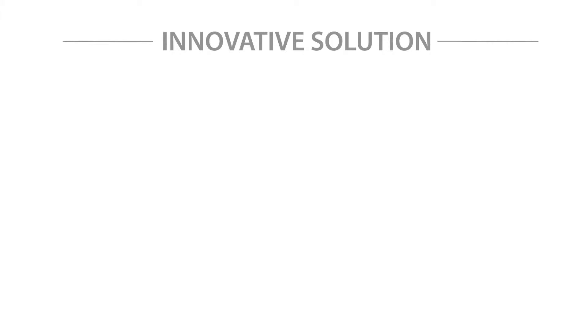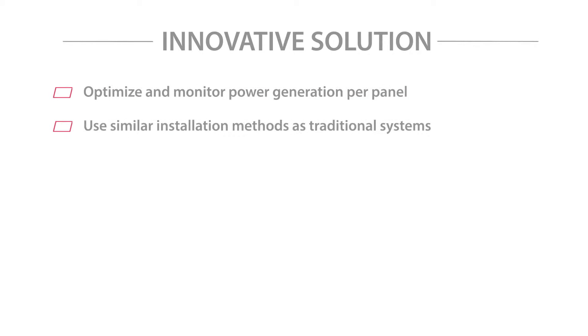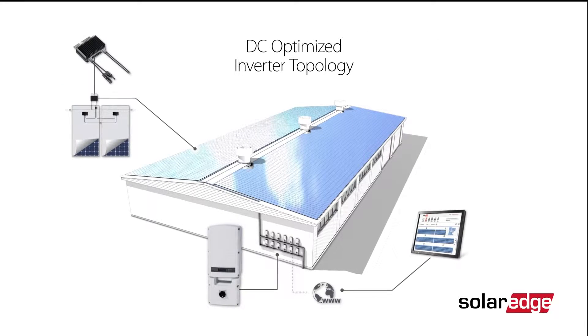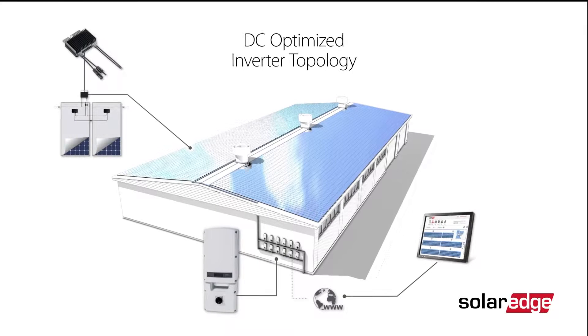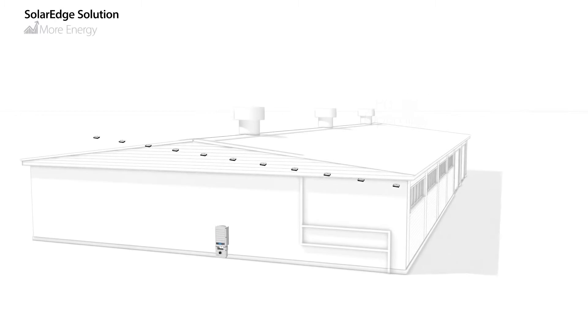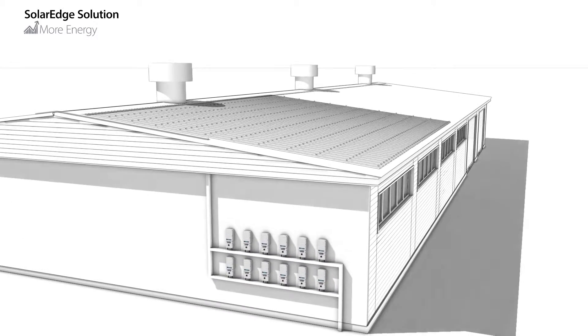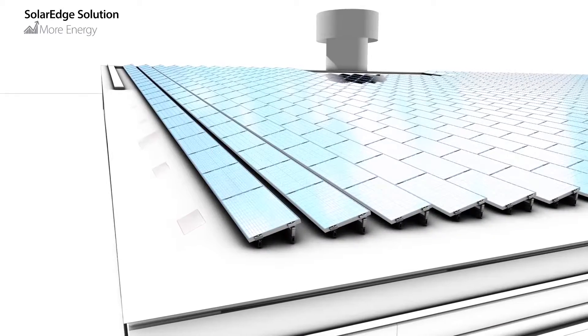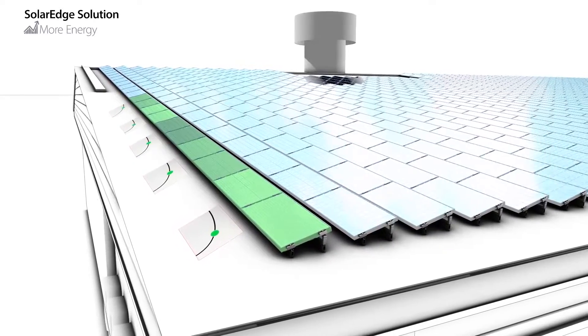When we started to develop the SolarEdge solution, we looked at the challenges posed by traditional systems and defined three goals: to optimize and monitor power generation of each panel; to use the same installation methods and components used to install traditional inverter systems; and to minimize long-term operation and maintenance costs. We developed a topology that meets all of these goals — the SolarEdge DC Optimized Inverter Topology. Our solution splits the traditional inverter functionality into two products: the power optimizer and a simplified inverter. The power optimizers are located on the panels, turning them into intelligent panels. These power optimizers maximize system output by providing panel-level tracking and real-time adjustments of current and voltage to the optimal working point of each panel.